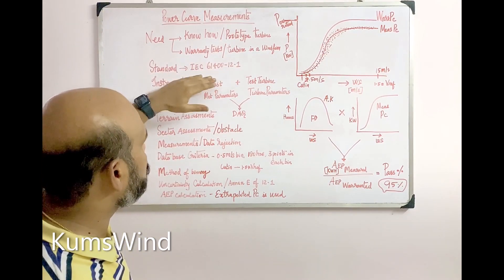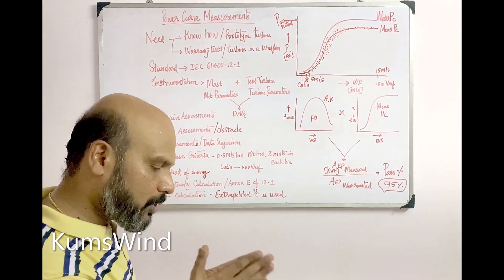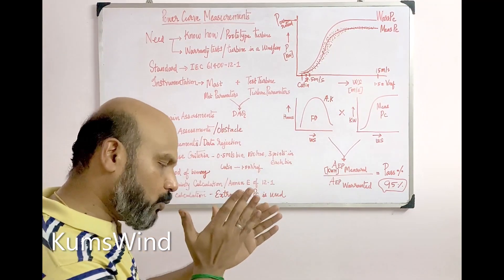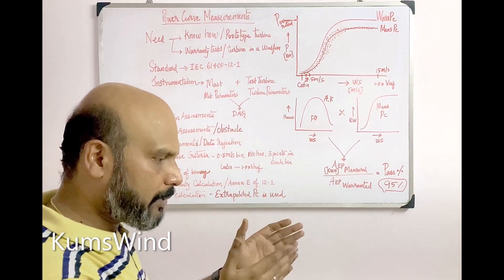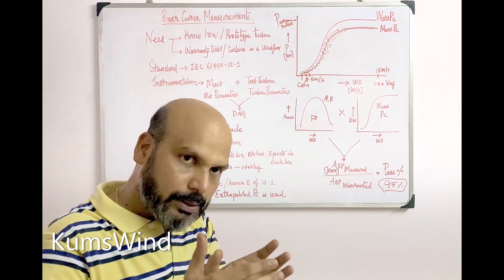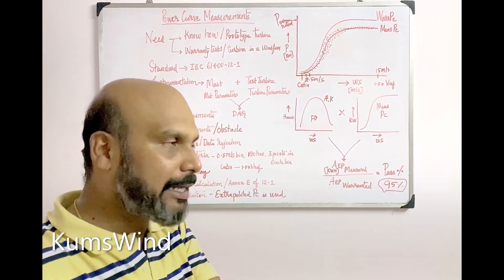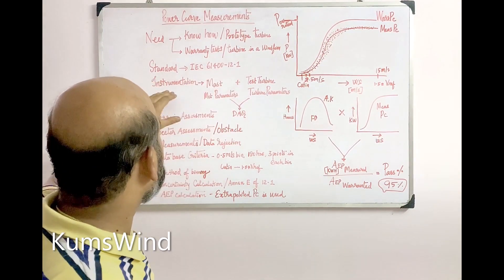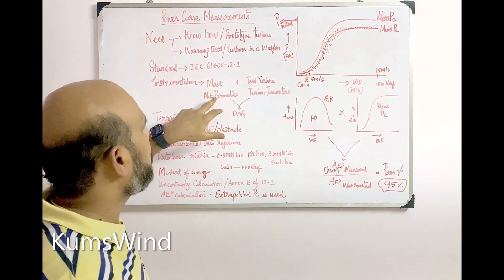The standard which governs the whole process is IEC 61400-12-1. This standard covers all stages and activities involved in power curve measurement, starting from the selection of instruments, to the sampling frequency, to the accuracies of the instruments, to the measurement process, the data analysis process, uncertainty calculation, and AEP calculation. Everything is well defined and explained by the standard.